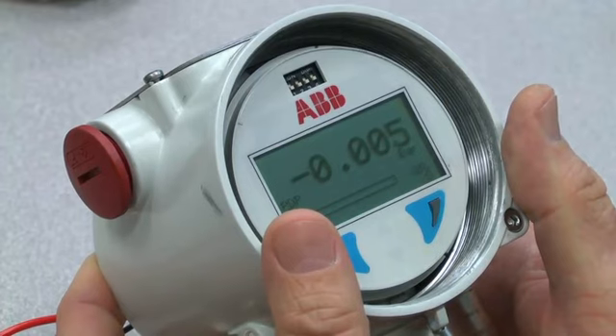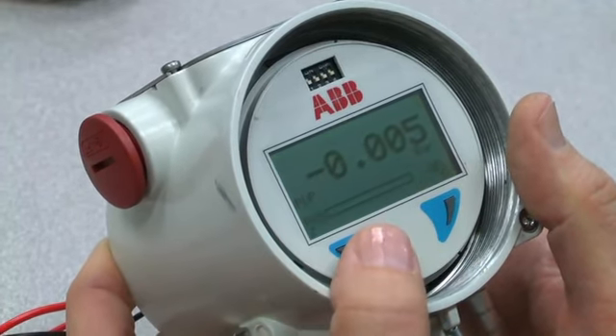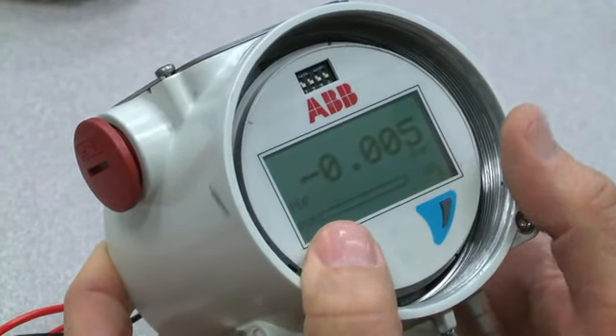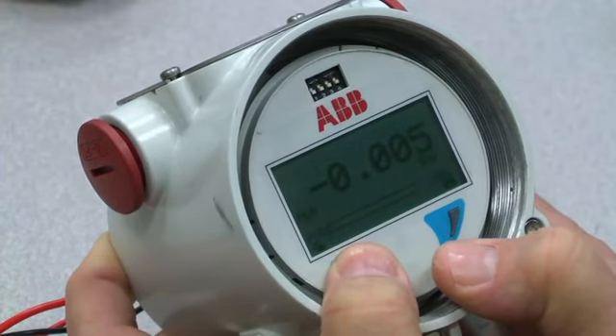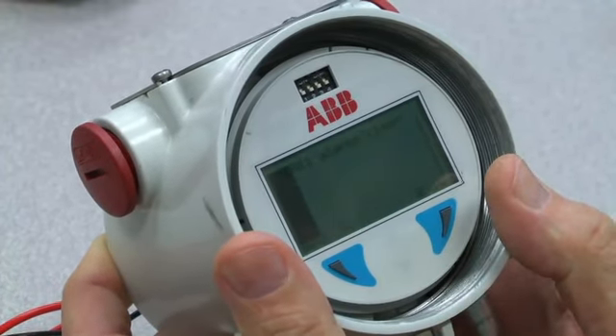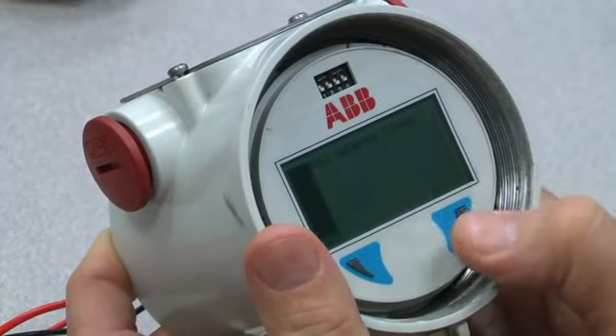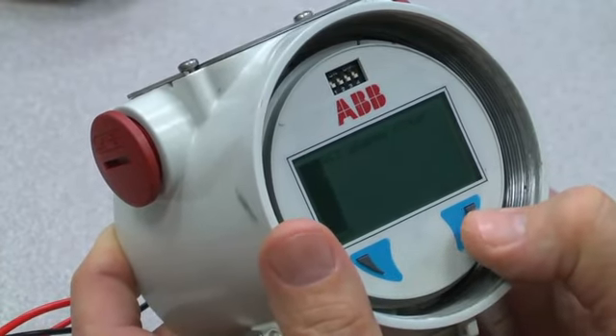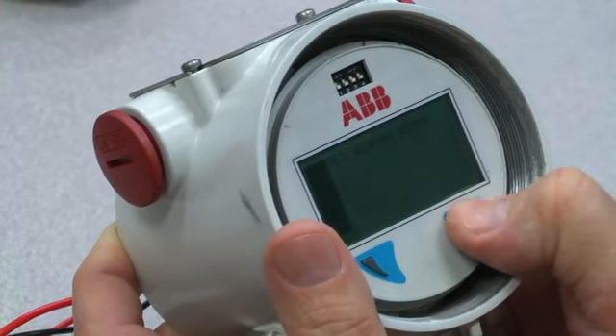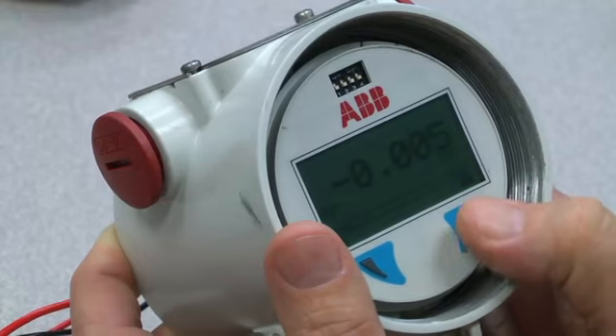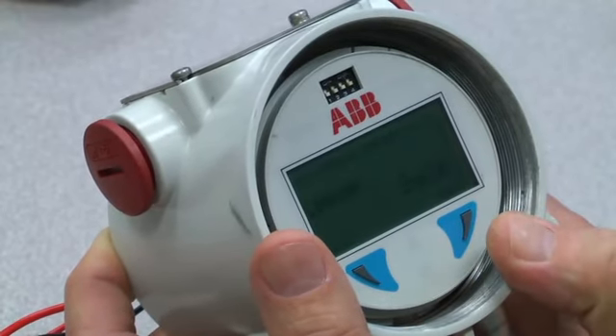Okay, I'm going to start with the menu items here. You can see the left button is labeled Z and the right button is labeled S on the screen. I'm going to hold them both down at the same time for 5 seconds, and that's going to enable the menu items. If you push the Z button, that takes you directly into the diagnostics. Now you can see here we don't have any alarms, so we don't have any diagnostics to check or to clear. And then I'm just going to go next here, exit here, go back to the main menu. Then I'm going to hit the S button to go back into menu, and now we're in the easy setup.